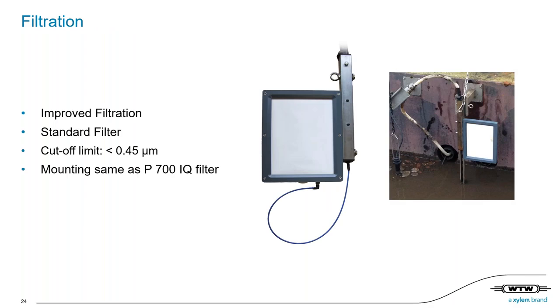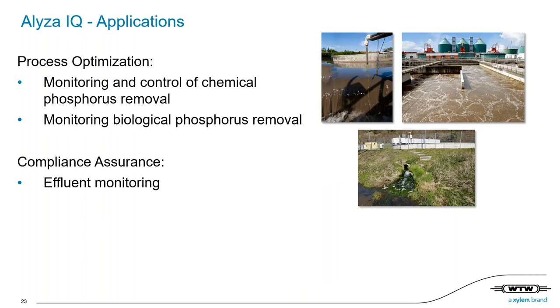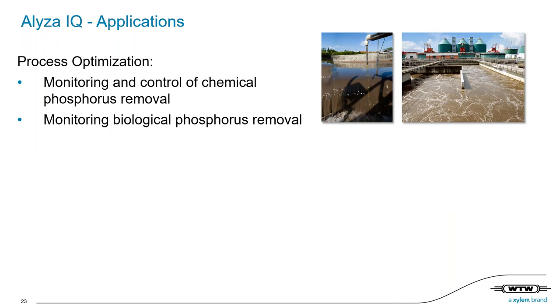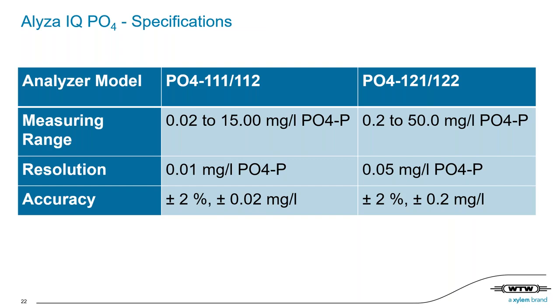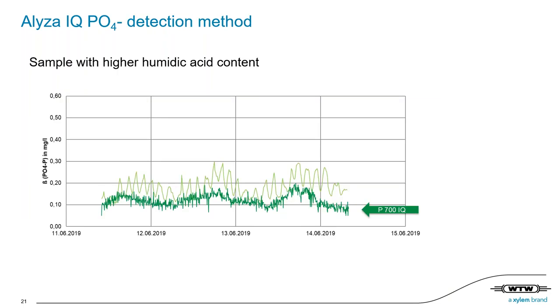So we have one of the status displays what you have in the new software. So maybe one word to the software. So our former analyzer, the P700, has the normal user interface for the IQ SensorNet. And what we did for the Alyza, we really optimized the software, and also there are self-diagnostics, so onboard diagnostics and everything included. So this is really full transparency. And for the reagents, as I said, you could purchase a spare one, but if you have a 20 minutes interval, it lasts 1 year, or a 10 minutes about half a year, and you will always have the transparency via the display to see when you need an exchange.